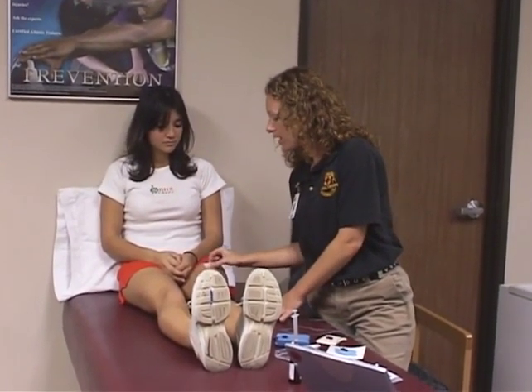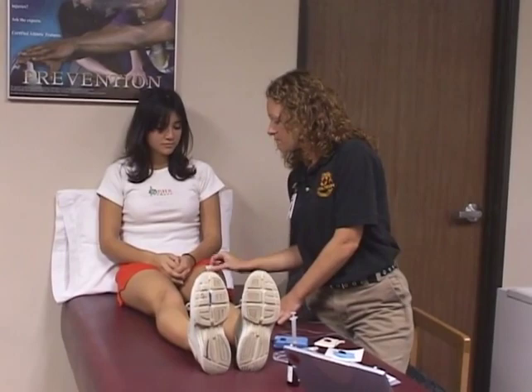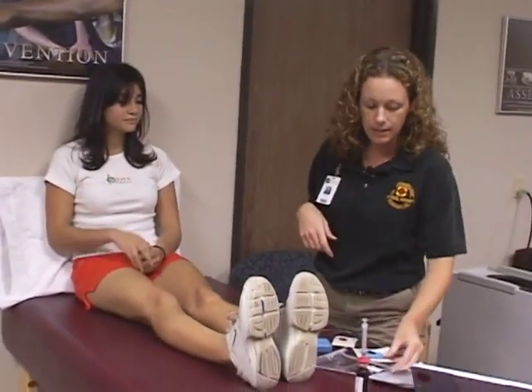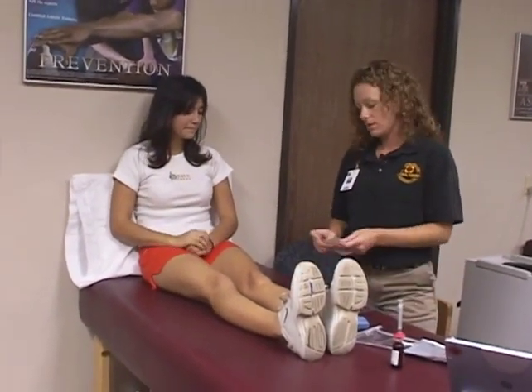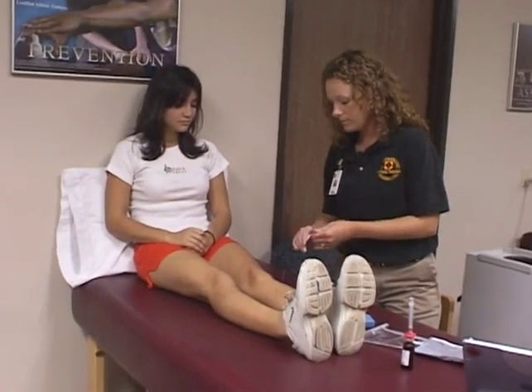And then you're going to find a nice, big, muscular surface to attach your ground pad. It could be here, we're going to use the quad. It could be the calf. You could actually use the opposite limb. It really just depends on your preference. I'm just going to make sure that it's dry here so we get it nice and sticky.